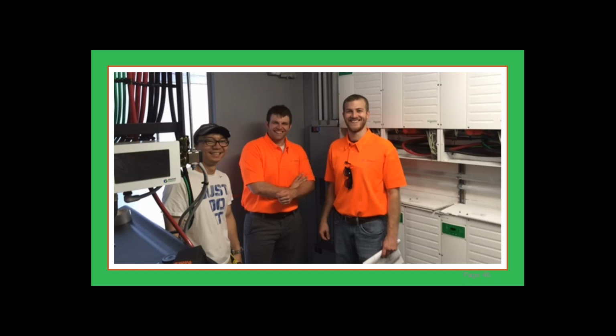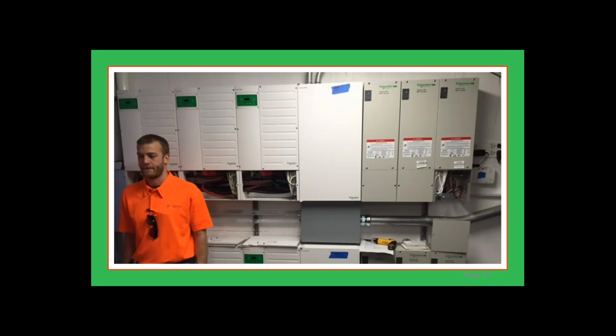Here we see a 6XW system at the Institute of Technology in Chicago. We have one ComBox dedicated to the 6XW Plus inverters and a second ComBox dedicated to the 6 MPPT80 charge controllers. There's also a secondary backup system in the north battery room that also has a dedicated ComBox. So when we're talking about using multiple ComBoxes, there's a limit to how many Xanbus devices that you can accommodate in a single network. So that's why we offer the ability to have master and slave ComBoxes.